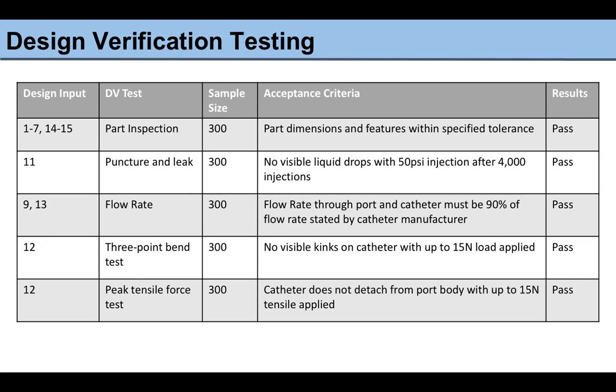Our fourth test was a 3-point bend test, where we wanted to ensure that no visible kinks were on the catheter when up to a 15 Newton load was applied. This test passed. And we also performed a peak tensile force test, again where we loaded the device up to 15 newtons and ensured that the catheter did not detach from the port body, which also passed.